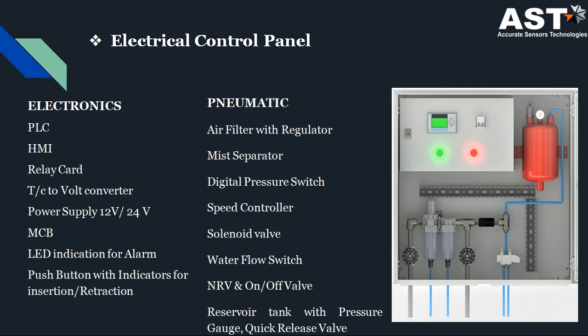Then the relay cards are there, the voltage converters are there, and the power supply for the PLC and HMI is given. Then some MCBs and electrical switchgear points are there. The LED indications are provided on the panel itself, along with manual push buttons for insertion and retraction of the monitoring system. Then in the pneumatic series, we have the air filtration system, where we are using the water cooling system and the air for the purging or cooling purpose. Through the air filter and regulator, we give the supply to the system. Then we have a digital pressure switch, speed controller, and solenoid valves to operate the retraction system, and a water flow switch, NRV valves, and a reservoir tank in case the water system or the air purging and air cooling system fails. So we have a reservoir tank to retract the furnace monitoring system out of the furnace for safety purposes.